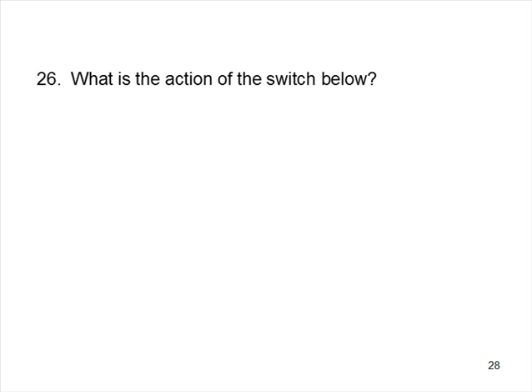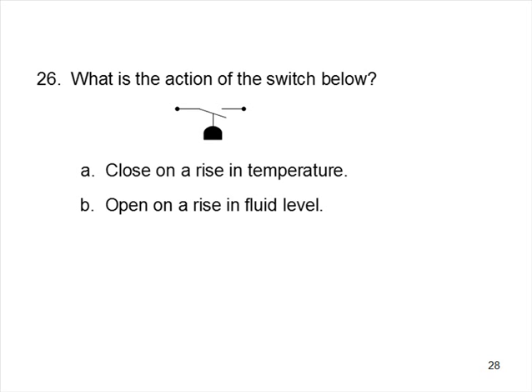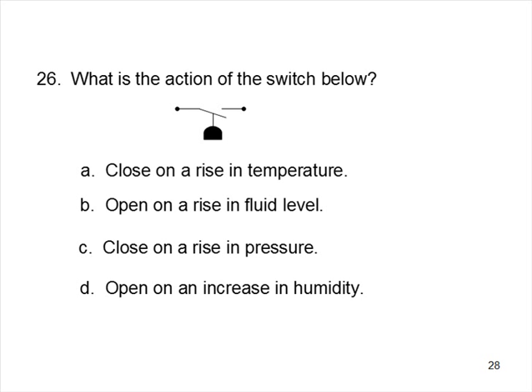26. What is the action of this switch below? Here's the switch. What action does that switch take? Closes on a rise in temperature, opens on a rise in fluid level, closes on a rise in pressure, and opens on an increase in humidity. When you look at that switch on a schematic, what should pop into your brain? Yeah, it's a low pressure switch. And it's a control. It shall normally open. And when the pressure gets high, it's going to close. And when the pressure gets low, it's going to open. Okay? Make, break, open, close, similar.